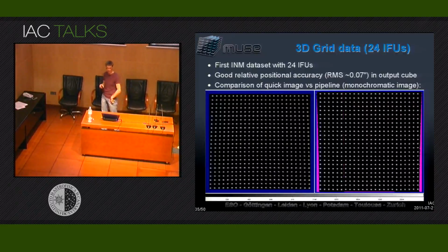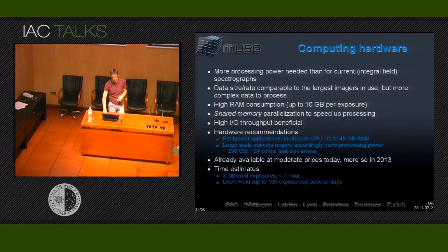So this was data with only one of the IFUs. In the meantime, the simulation software has evolved and can produce data from all 24 IFUs. And this is the first data set that we worked with. It was just here to show that the raw data somehow contains this rhomboid shape, which is due to some optical effects in the instrument. And after you run the pipeline, you get an almost perfectly rectangular grid of these sources. And they are, at least in relative terms, exactly where they should be. And they also have the correct full width at half maximum in the output and the correct flux in the output. So I'm pretty happy with how the pipeline performs on this.